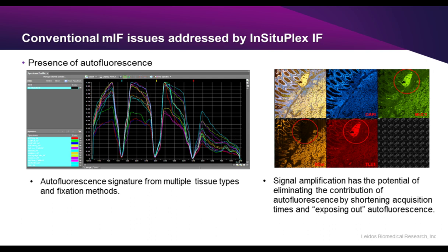Is there a problem with eosin autofluorescence interference when multiplexing on an H&E slide? When we actually run the H&E of a multiplex fluorescent slide, we run our multiplex fluorescent assay first, capture that image once satisfied with image quality, then run the eosin — the H&E — afterwards and acquire your bright field image. Once you've stained with eosin and hematoxylin, you really won't be able to go back to your fluorescent aspect and reimage it. So it's important to capture your fluorescent image before starting the H&E process.